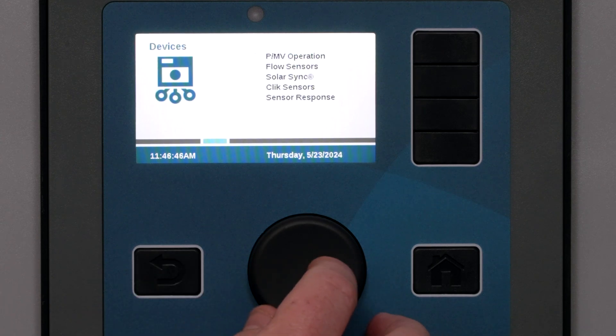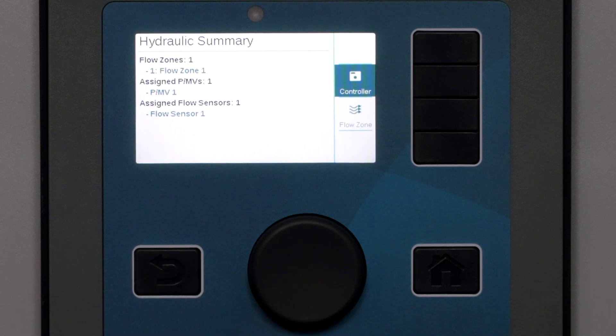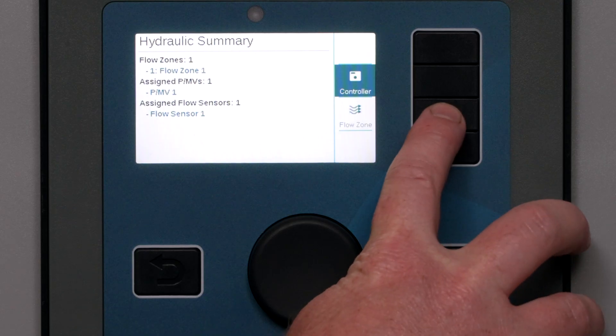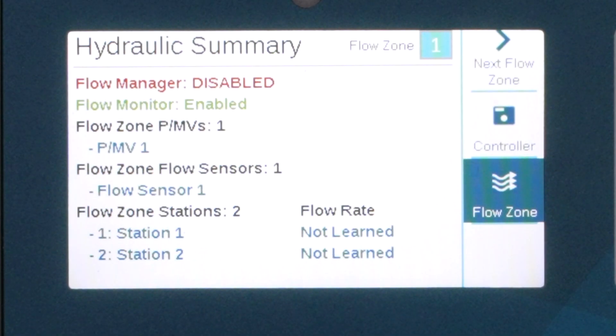At the controller level, the Hydraulic Summary will show you how many flow zones are configured and what devices have been configured. Click the Flow Zone key and this screen will show the complete configuration of all devices in the selected flow zone. You can review all of the PMVs, flow sensors, and stations that have been attached to the flow zone. You can then correct any mistakes or omissions. If there are multiple flow zones, use the next key to advance through each of them. Once the controller has learned flow, this screen will also show the learned flow for each station.